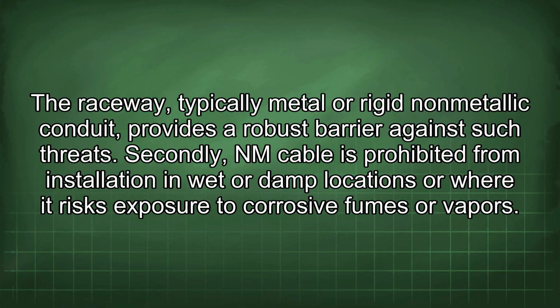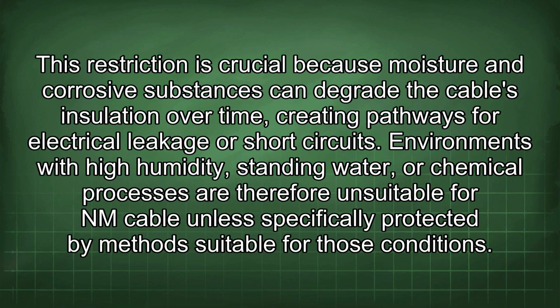Secondly, NM cable is prohibited from installation in wet or damp locations or where it risks exposure to corrosive fumes or vapors. This restriction is crucial because moisture and corrosive substances can degrade the cable's insulation over time, creating pathways for electrical leakage or short circuits.